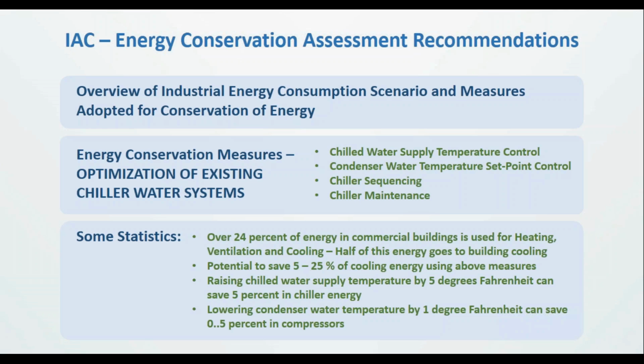And the sequencing of it and then the condenser profile can also be looked at in terms of temperature set point. The sequencing, as I mentioned, occurs when you have multiple chillers and multi-stage chillers, and we take a look at the load profile in terms of sequencing. What a sequencer essentially will do is try and run these chillers at as maximum load as possible, and then possibly suggest ways of trimming the final element in the chiller system so that we can try and reduce the energy consumption. Now when it says to trim, sometimes the chiller that is trimming might be very much underloaded. So that opens up a situation of load sizing of that chiller. Maybe it is too big for operation under these constraints of the manufacturing parameters. So that opens up the possibility of thinking about downsizing that chiller.